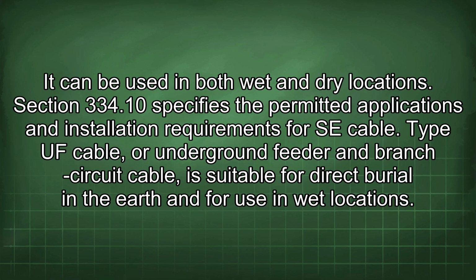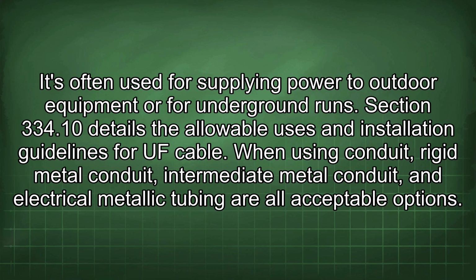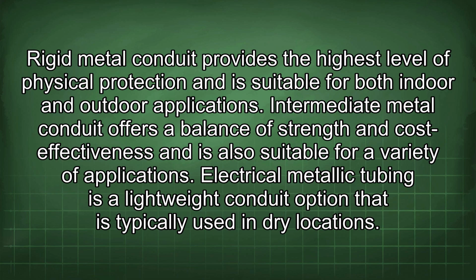Type UF cable, or underground feeder and branch circuit cable, is suitable for direct burial in the earth and for use in wet locations. It's often used for supplying power to outdoor equipment or for underground runs. Section 334.10 details the allowable uses and installation guidelines for UF cable. When using conduit, rigid metal conduit, intermediate metal conduit, and electrical metallic tubing are all acceptable options. Rigid metal conduit provides the highest level of physical protection and is suitable for both indoor and outdoor applications.